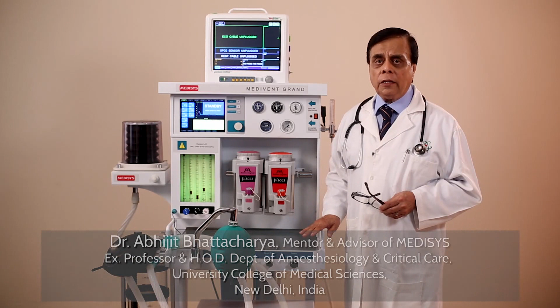And to do that, we have to have two devices. One is a safety device and second is the capability device. We talk about the safety device. The most dangerous thing which any anesthesiologist dreads is lack of oxygen delivery. To counteract that, we have several devices inbuilt into our machine. One of them is the oxygen ratio controller. Second is the oxygen failure protection device, and on top of that we have an inbuilt oxygen analyzer. Now this oxygen analyzer also can be interpolated between the inspiratory system and the expiratory system wherever, so that you can know the expired oxygen concentration also.